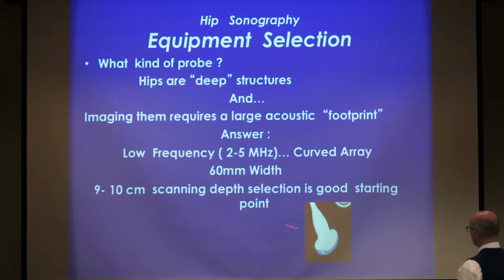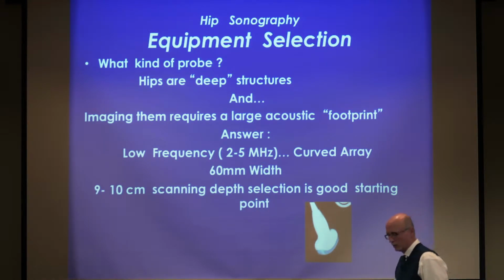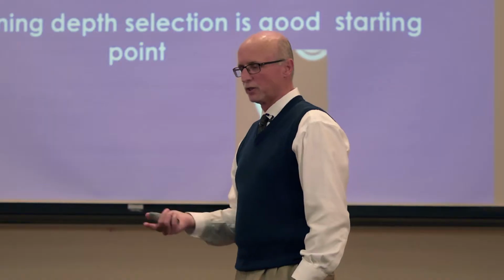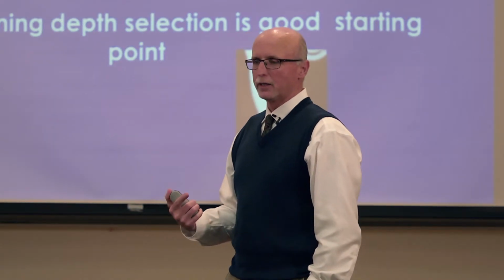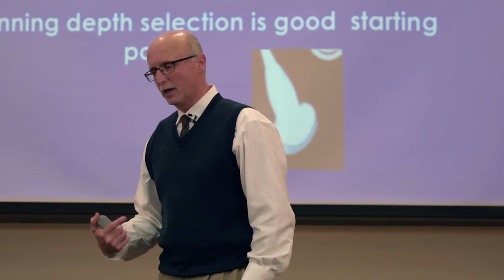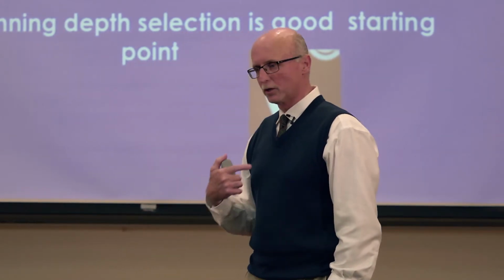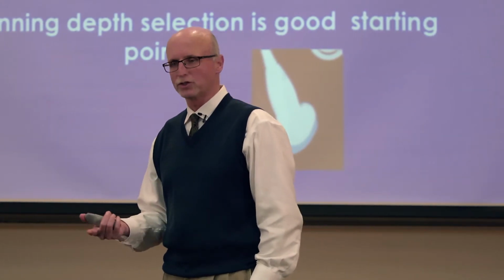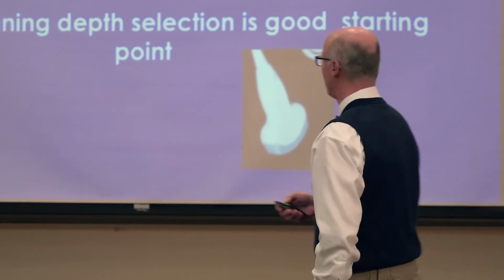As far as a preset depth, typically I use a 9 centimeter scanning depth. The reason I mention that is because usually when the curved array probe is activated on an ultrasound system, the ultrasound system thinks you're looking for a baby, doing obstetric scanning, so the depth will default to something like 18 or 20 centimeters, and there's just no need to have all that depth.